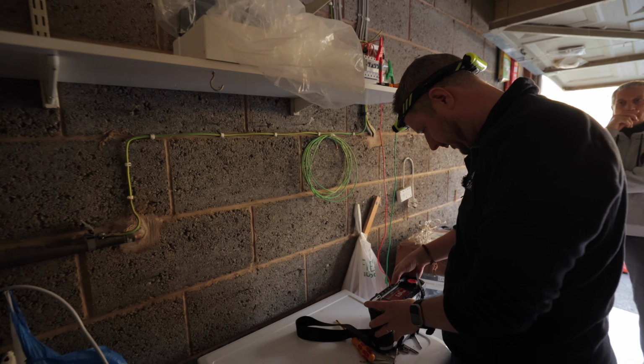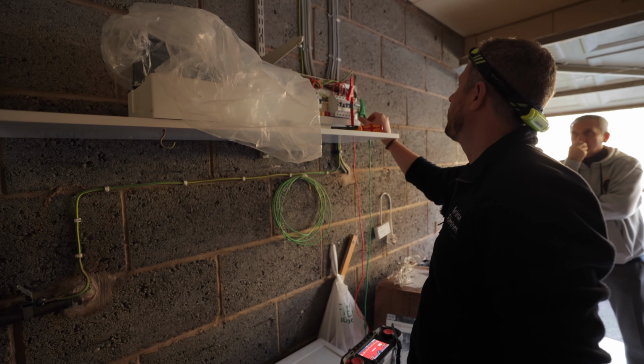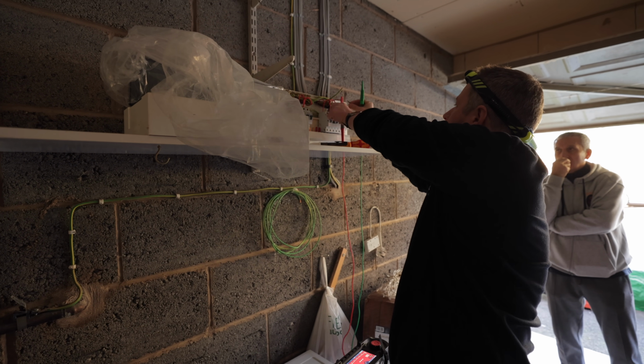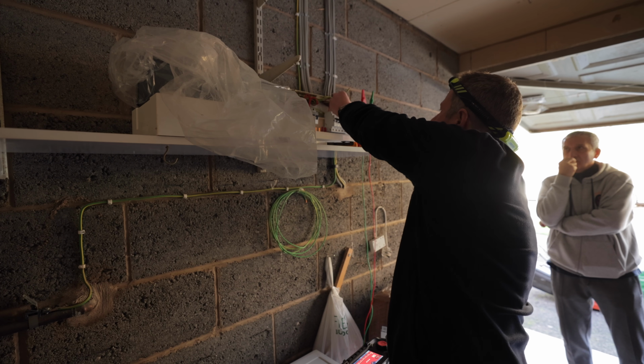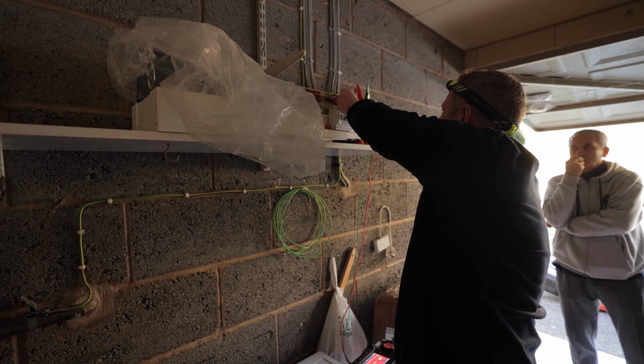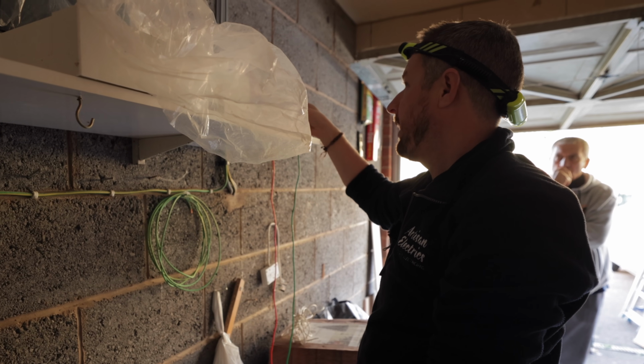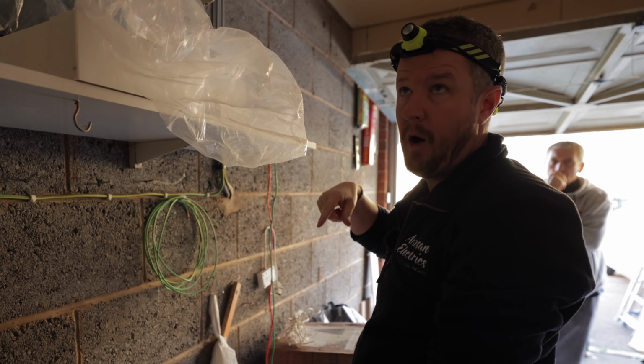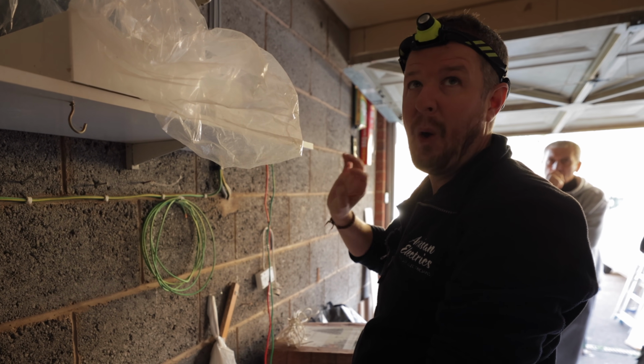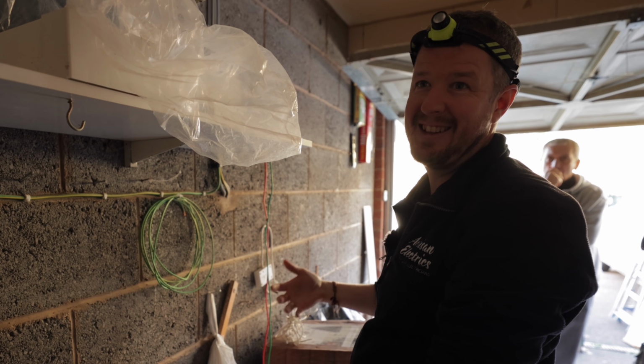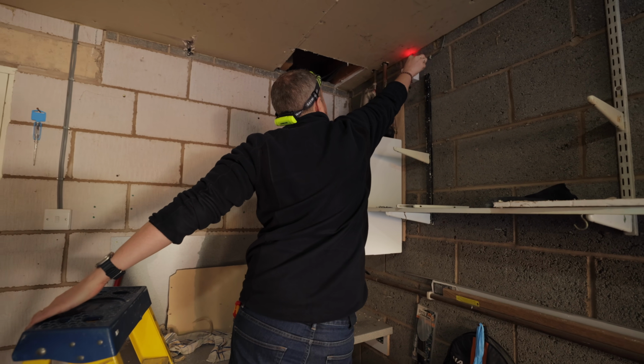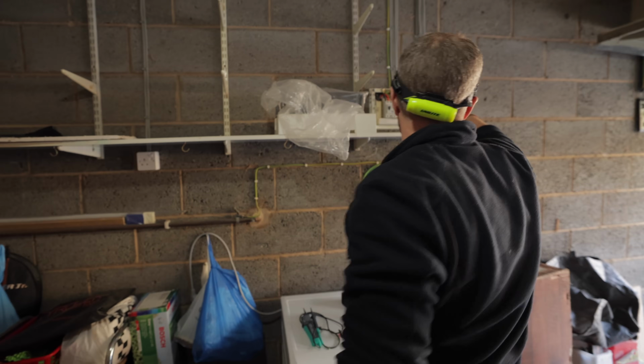I'm going to up the voltage on this test to 500 volts, and I'm just going to put line and neutral together and test them both to the earth. Yeah, it's still all clear, but it could be that when we turn the circuit off, the item that's got the fault in it is disconnected, and therefore the fault doesn't show anymore. Yeah, that's on at the moment. Try that.